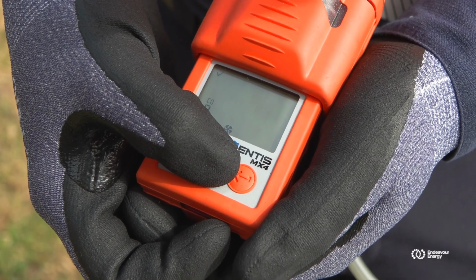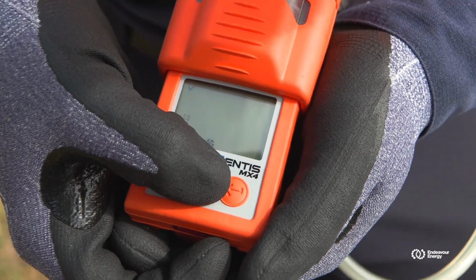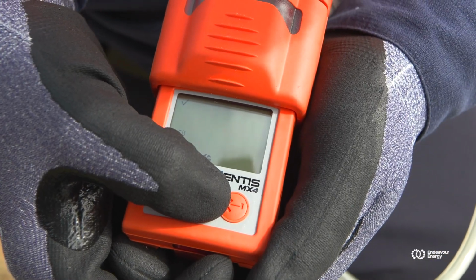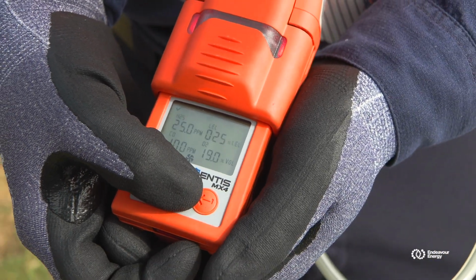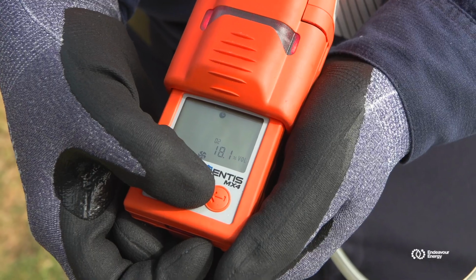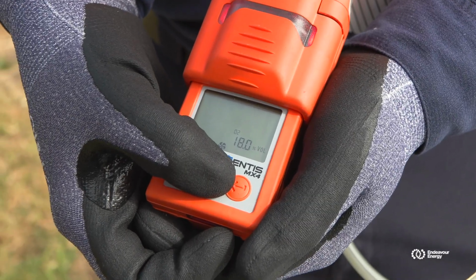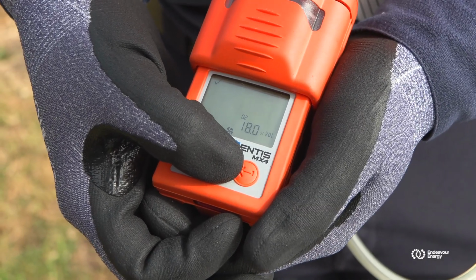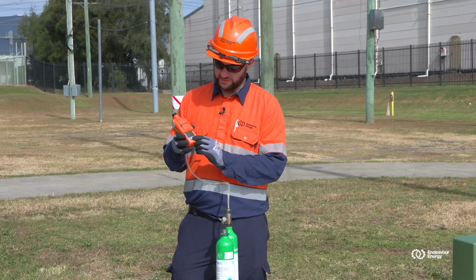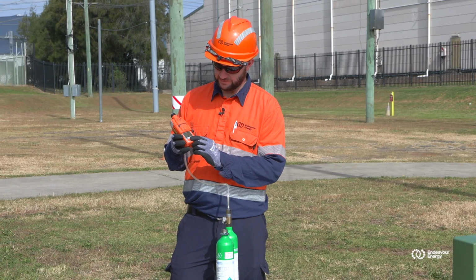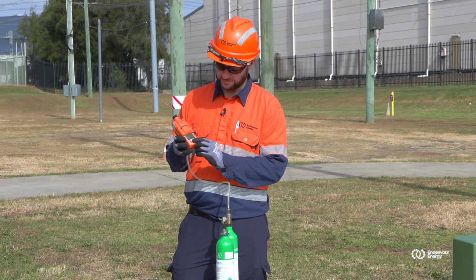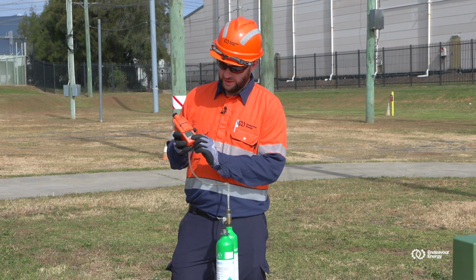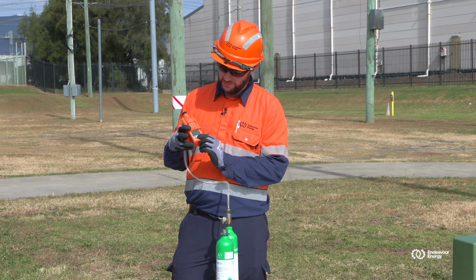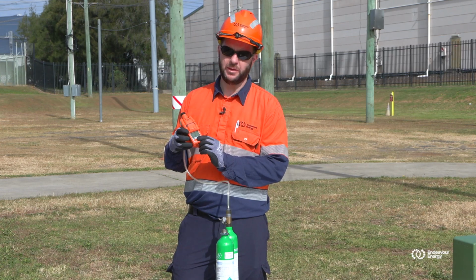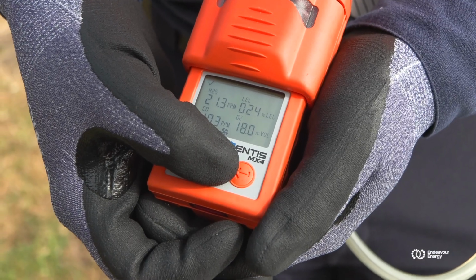Now we're testing the carbon monoxide sensor. Once again, it's displayed a P for pass. And finally, we'll move on to the oxygen sensor. And once that's done its test, it'll display a P for pass as well, or an F for fail. In this case, we have a P for pass. Now on the screen, we have an image which shows all four sensors with P's under all of them to say that the unit has passed.